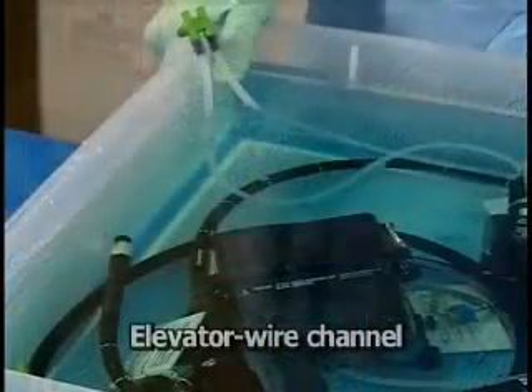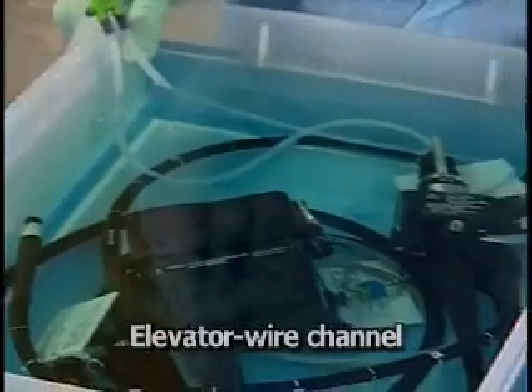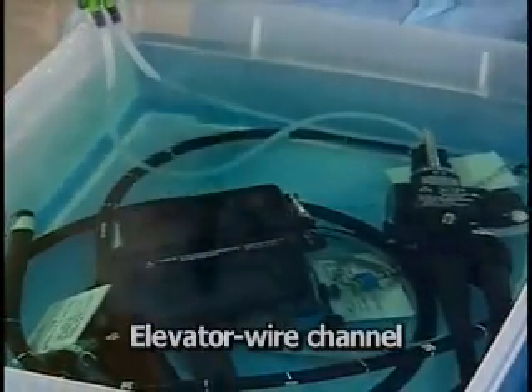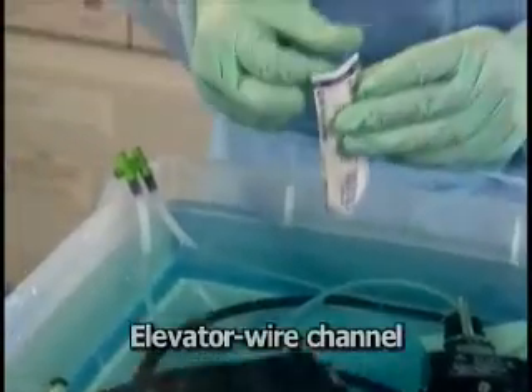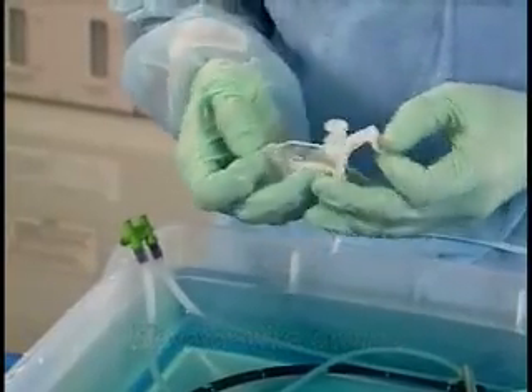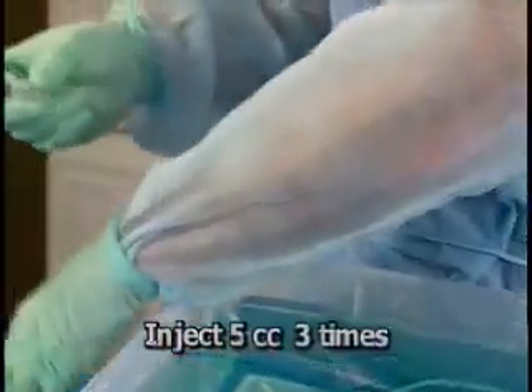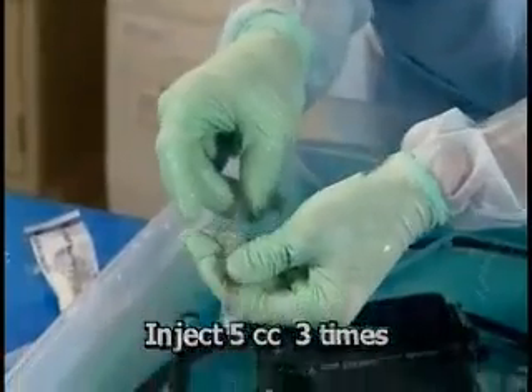If you are reprocessing an endoscope with an elevator channel, inject air to expel disinfectant from the elevator wire channel using a 5 cc syringe at least 3 times.